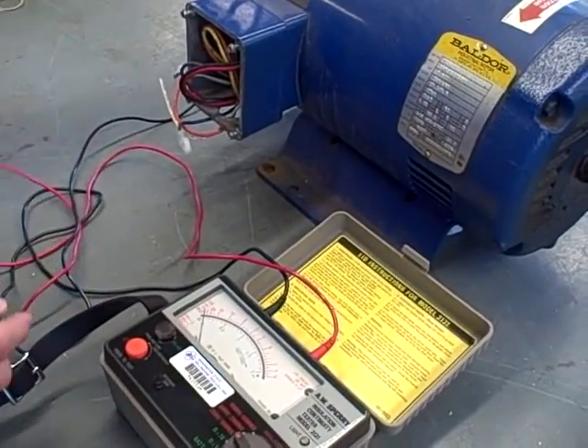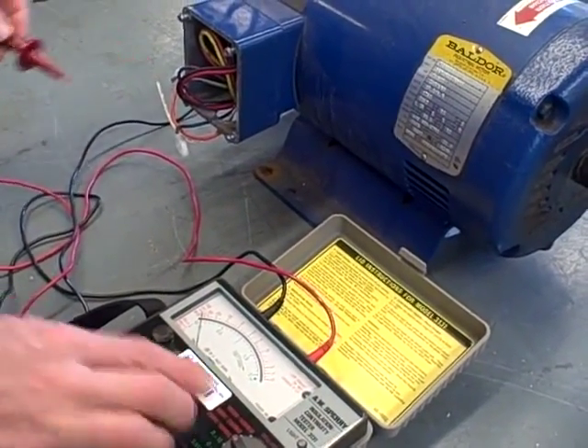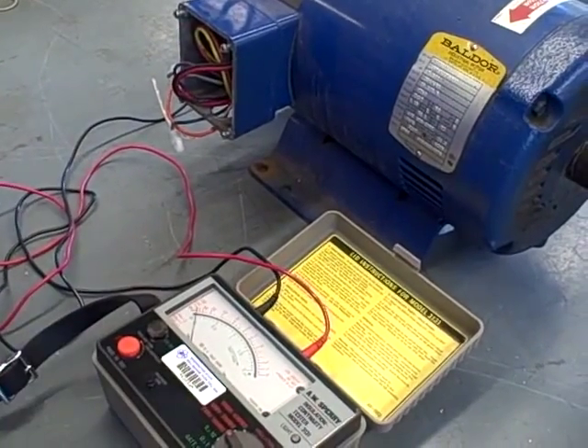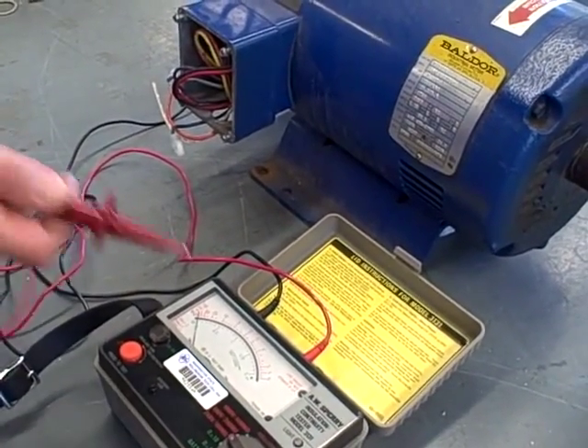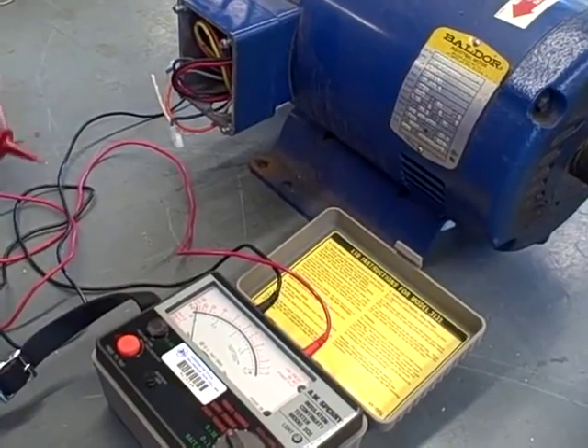So clearly, I can see there's a fault in this motor using a high voltage setting that I don't see with a low voltage setting. And that is the unique value of a Megger style insulation tester.